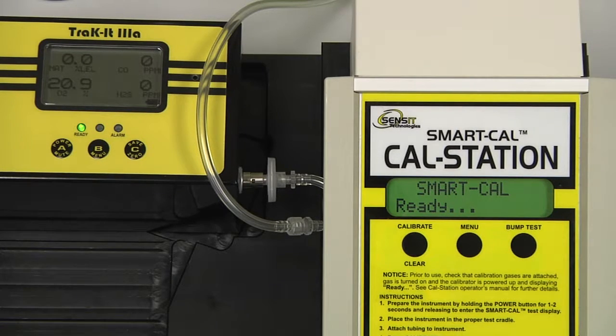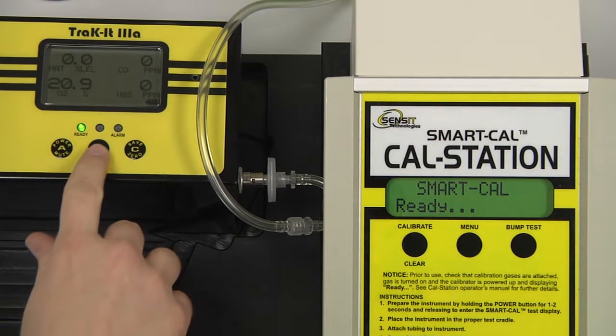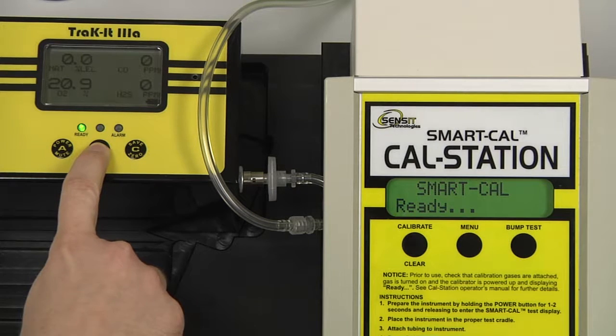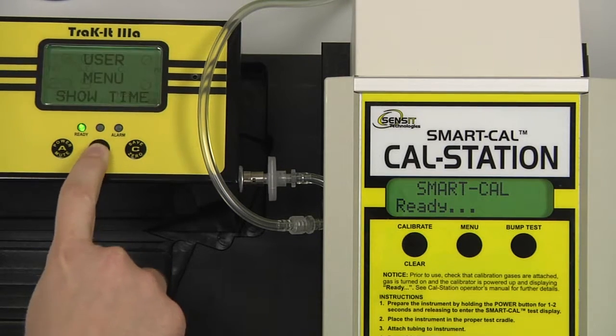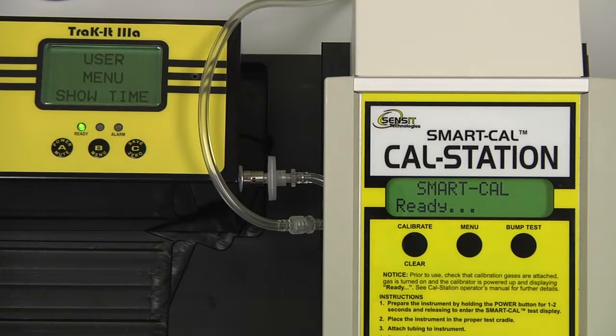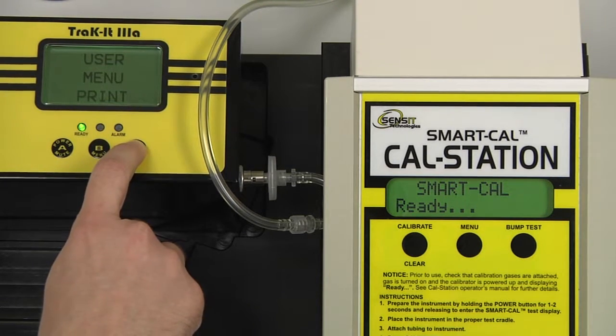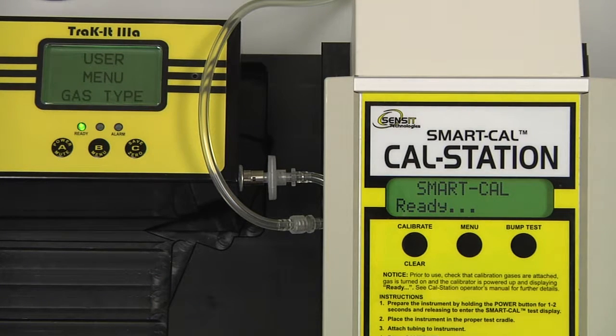The cal station will calibrate for either methane or propane, depending on the gas type selected, and cannot automatically calibrate for both. If we want to change the gas type, we can enter into the user menu by pressing and holding the B button, and scrolling by pressing and releasing the C button until gas type appears on the bottom line. Select by pressing and releasing the B button, and our currently selected gas type will be displayed, in this case natural gas or methane.